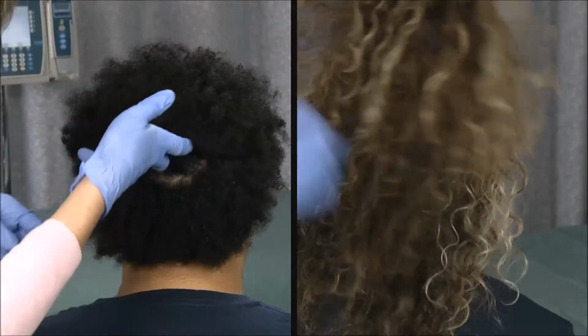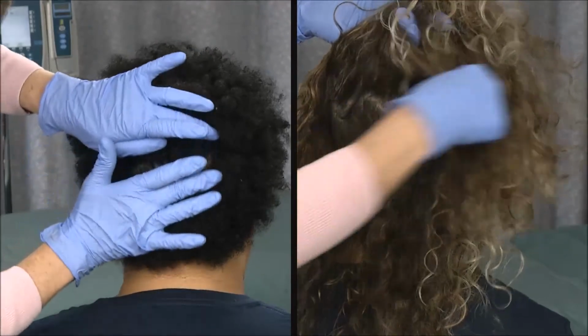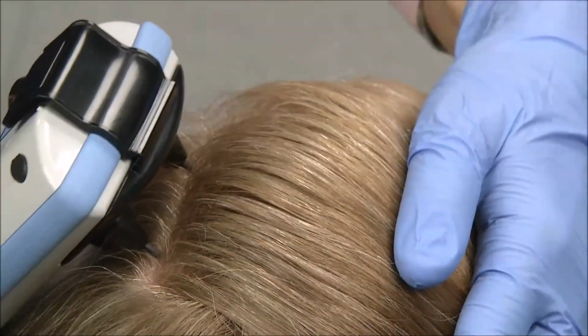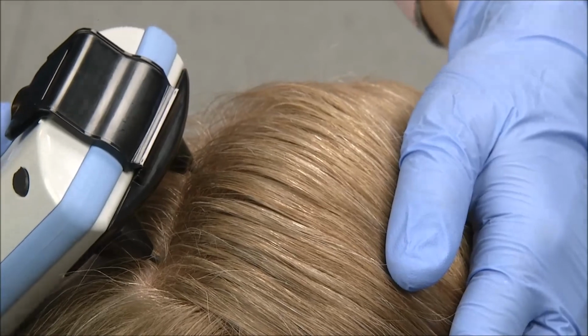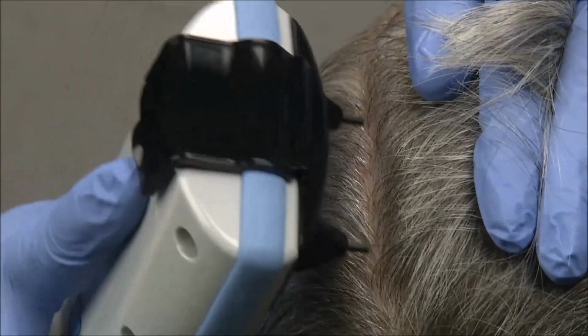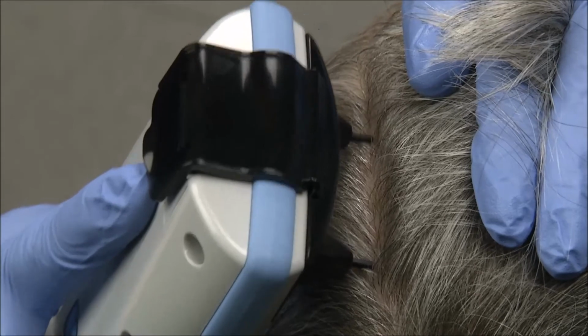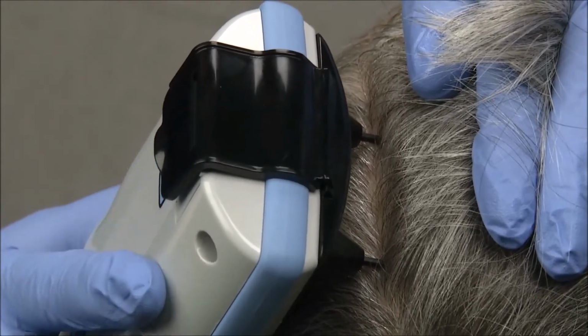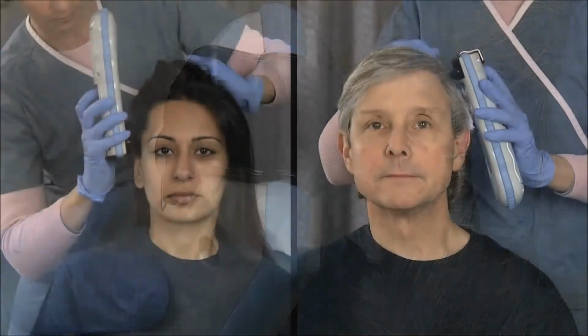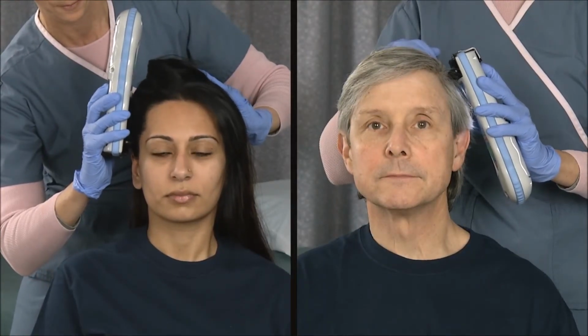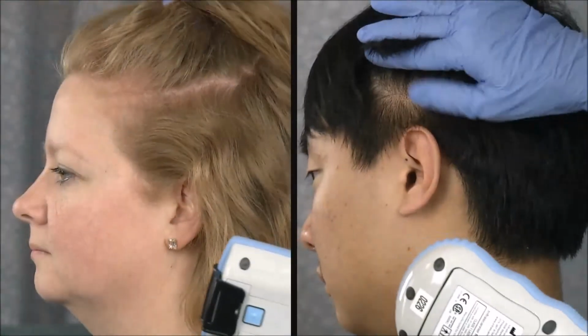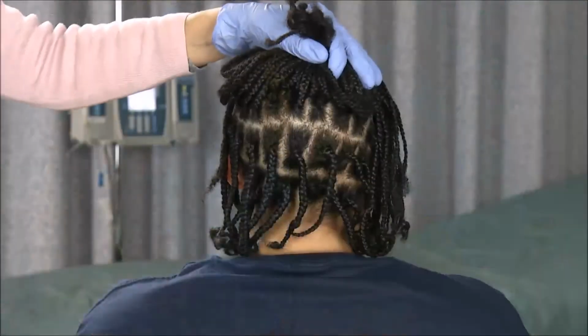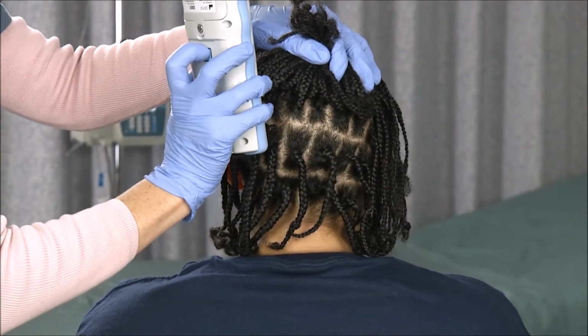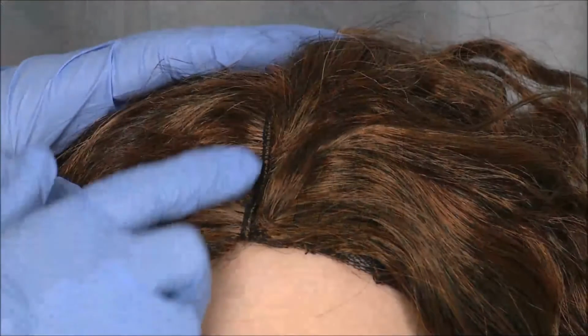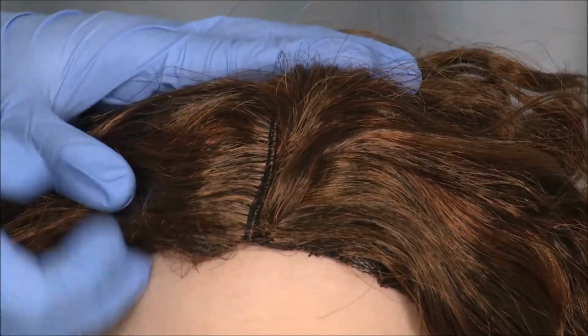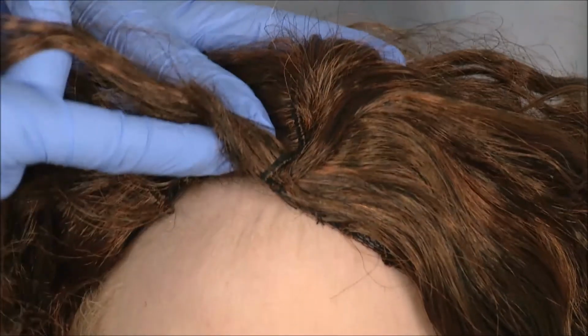Different hair types pose different challenges to achieving ideal scalp contact. One technique that will be consistent regardless of hair type is the need to gently comb or wiggle the fiber optic shield tips in the measurement locations to ensure there is no hair trapped under the tips. Different pigments of both hair and skin reflect light differently and can therefore affect the measurements. Getting good scalp contact with the probes is key to a successful scan. Please note that InfraScanner cannot scan through wigs, weaves, or toupees.